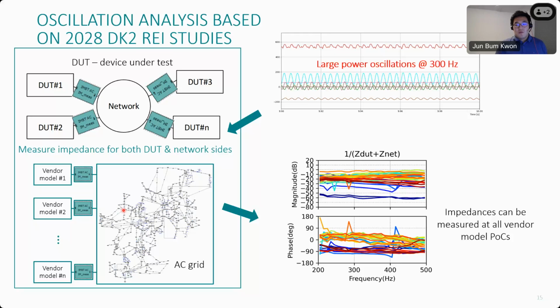So in this example, you can see some 300 Hertz oscillations we have observed in the time domain. We can see some impedance interactions through impedance network scanning, by perturbing the system and specific models towards the network. These features need a bit more effort to really mature, but we are developing them to support our system level EMT simulations and to figure out the main root cause of such oscillation or instability issues from a small signal stability perspective.